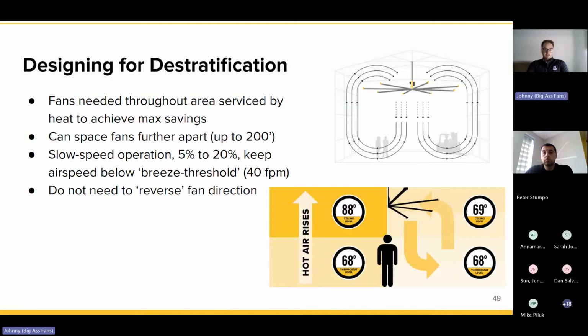destratification that we want. We also use that CFD modeling tool that you saw to make sure we're quantifying it, we're getting the right patterns of airflow, and we're getting enough turnovers in that space. I will call out here, do not reverse the fans. It is a much less efficient way to bring that warm air down. You're also blasting heat at your ceiling deck, which is the usual thinnest point of insulation. So what's going to happen there is you're just going to speed up the convective heat loss through your roof deck, and it's actually a negative impact to the building. So don't reverse the fans.